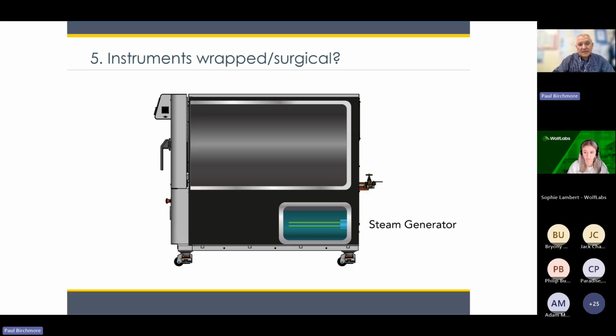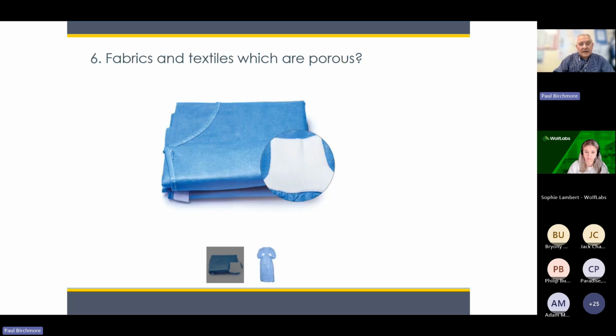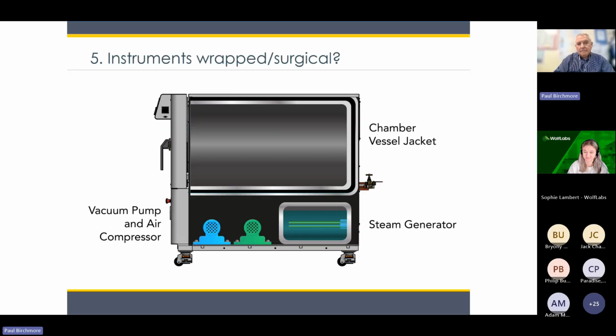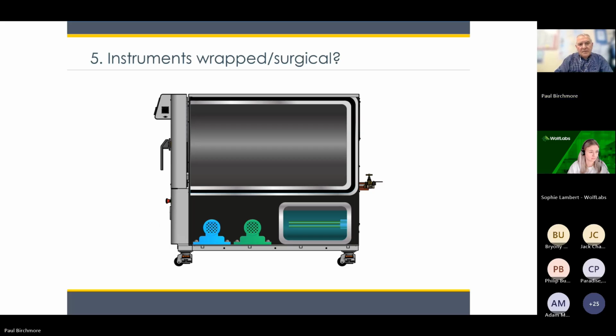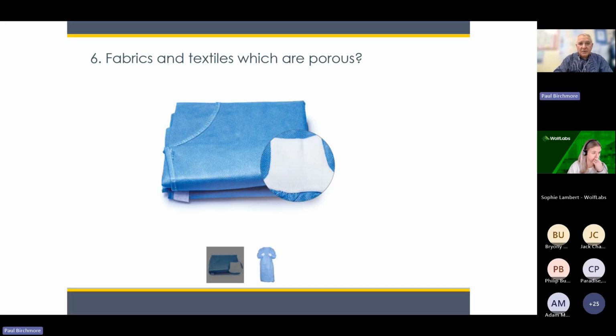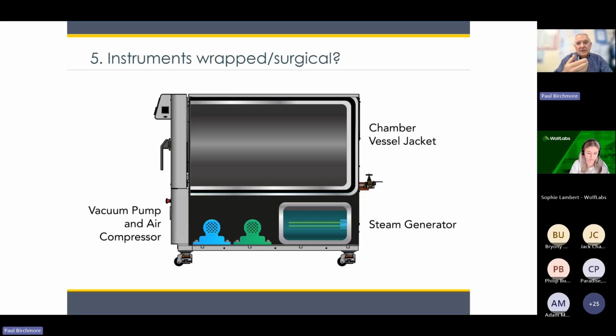So we move to the dry system, which is the one with the steam generating outside, the vacuum system. Oops, I shouldn't press that one. And then the chamber mechanism for heating as well. This is what we call the dry system, and you can only use the dry system for pouched items. Also, the final type of load is genuinely fabrics and textiles. They are clearly, evidently, a porous type of item. Those systems would require a dry system with the enhancements we touched on, the external generator, the dry system.